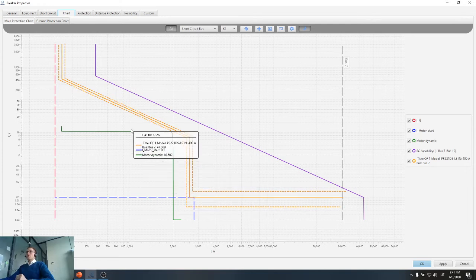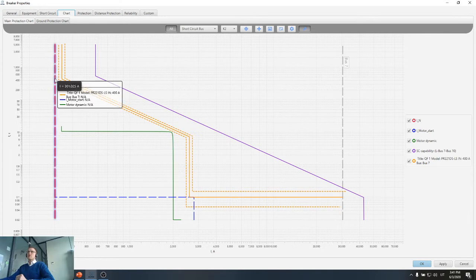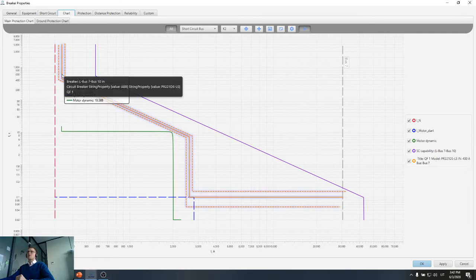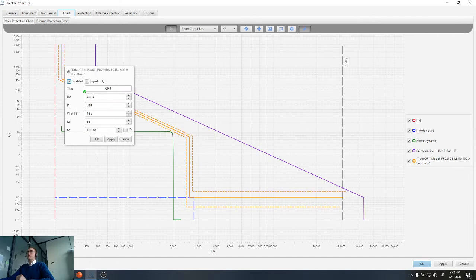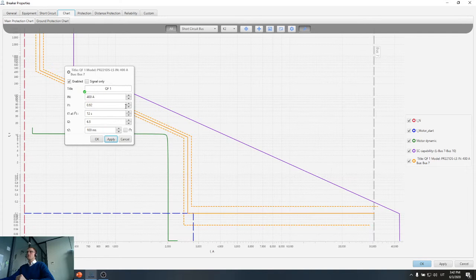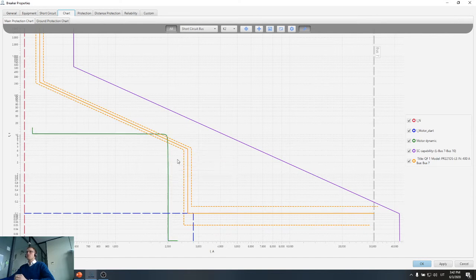First of all, we need to make sure that our protection device has enough safety margin between the normal operation current and our pickup current. So I can double click on the line and increase the current multiplier by choosing these arrow buttons here. I will increase the current multiplier maybe to 0.9 times the nominal current, and it is also possible to check whether it would be optional to reduce the time setting for my protection device, and maybe optimize protection coordination a little bit, because our main goal is to set protection devices sensitive enough to disconnect as fast as possible.